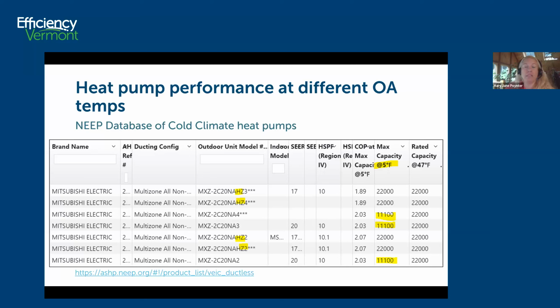So there's some sort of a balance there in terms of, do you want to spend more on multiple heat pumps? Do you want to spend more on a unit that can have full capacity at a cold temperature, versus undersizing because you already have a backup heating system? Now, they don't show you what it does at -11, but when you look on the NEEP database, you can see it'll stop at 5, and then if you have data for the colder temps, you can put that into the database tool, and it projects what it could be doing at those lower temperatures.